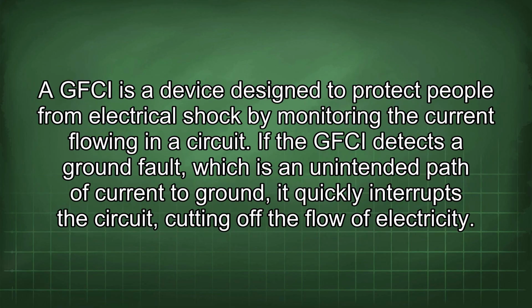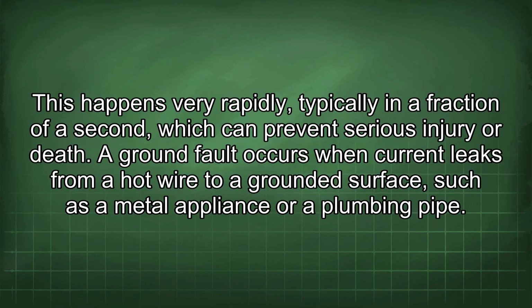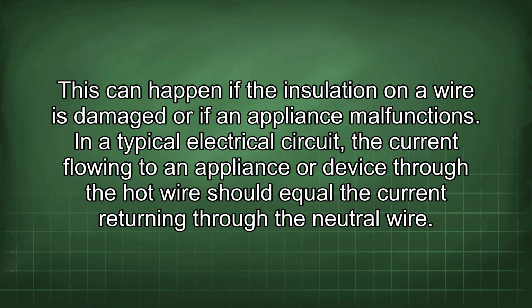A GFCI is a device designed to protect people from electrical shock by monitoring the current flowing in a circuit. If the GFCI detects a ground fault, which is an unintended path of current to ground, it quickly interrupts the circuit, cutting off the flow of electricity. This happens very rapidly, typically in a fraction of a second, which can prevent serious injury or death. A ground fault occurs when current leaks from a hot wire to a grounded surface, such as a metal appliance or a plumbing pipe. This can happen if the insulation on a wire is damaged or if an appliance malfunctions.